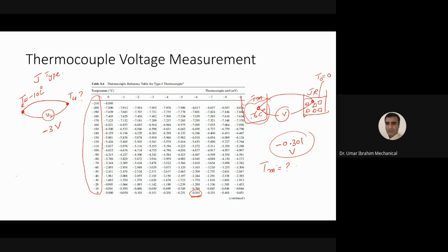सो व्हाट आई विल डू इन माय ओन माइंड, आई विल क्रिएट दिस थर्मोकपल सर्किट, और इसको मैं 0 डिग्री सी रेफरेंस पे ले लूंगा. ठीक है, नाउ अब -10 के लिए वोल्टेज कितना? -10 डिग्री सी के लिए यहां पर V1 की वैल्यू क्या होगी? -0.501. हाँ, -10 के लिए ये वैल्यू होगी. ठीक है, सो V1 विल बी इक्वल टू -0.501.